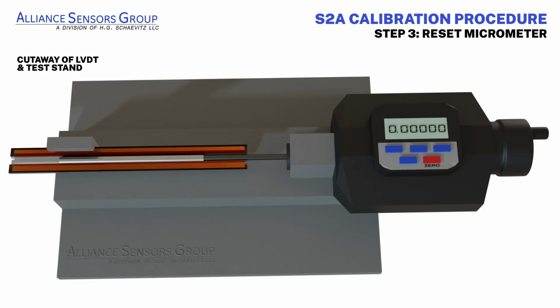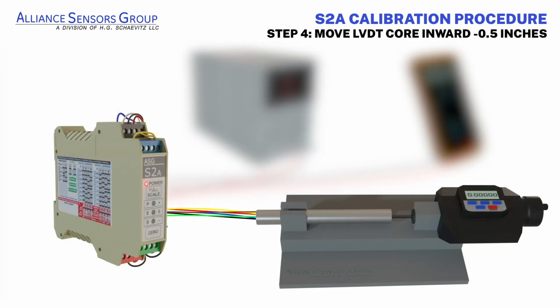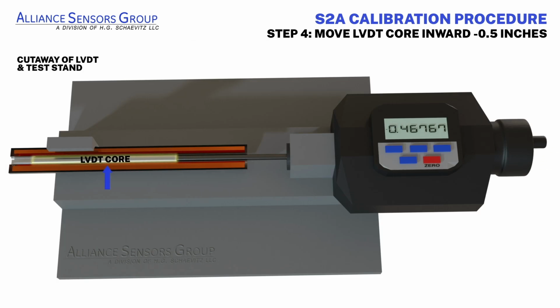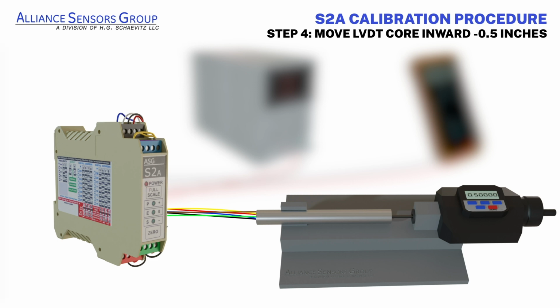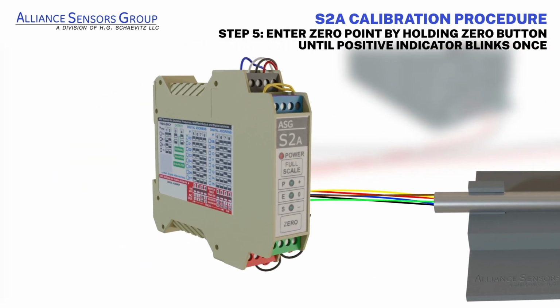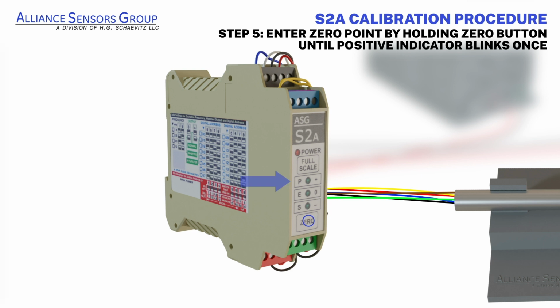Next, using the digital micrometer, move the LVDT's core inward to minus 0.5 inches. This will take us to the negative end or 0-inch core position of the LVDT stroke and will be the S2A's 0 volts DC output position. Enter the 0 point position into the S2A by momentarily holding the 0 button down until the positive indicator blinks once. The negative indicator will now glow solid and the positive indicator will begin to blink. This shows that we have successfully set the 0 point position.